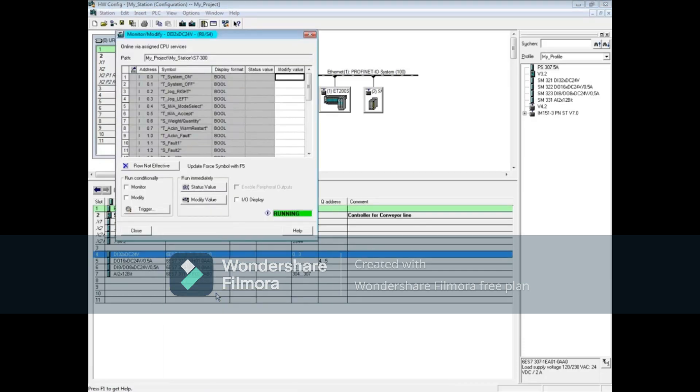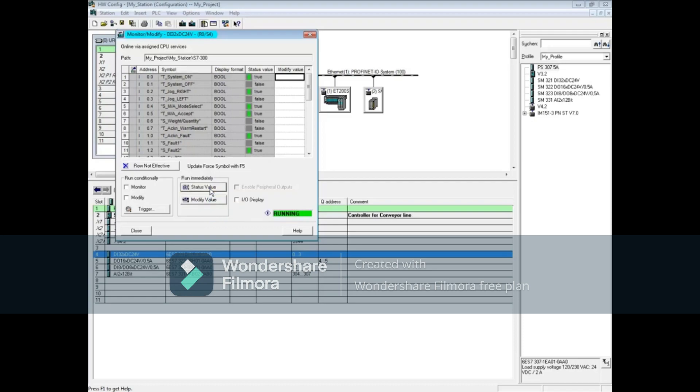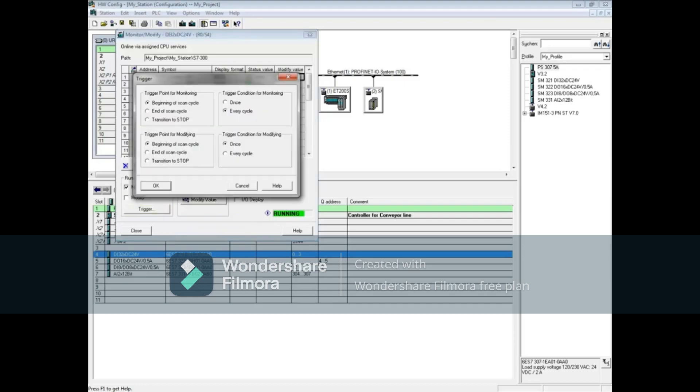For a single scan update, click the status value button. To update cyclically, click the checkbox next to monitor, then click the trigger button. By default, monitoring is done at the beginning of the scan cycle, which is what you want for inputs since they are read in at the beginning of the scan. The trigger condition updates every cycle by default.